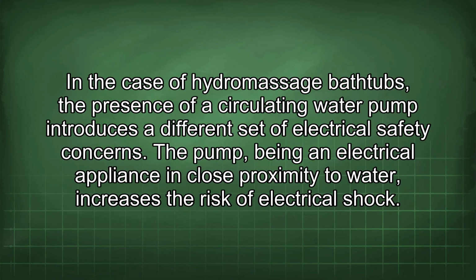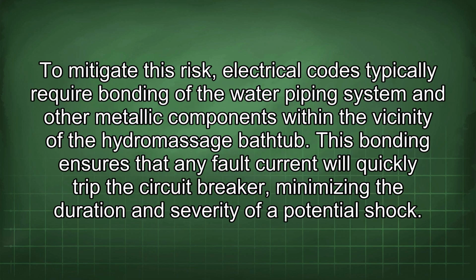In the case of hydromassage bathtubs, the presence of a circulating water pump introduces a different set of electrical safety concerns. The pump, being an electrical appliance in close proximity to water, increases the risk of electrical shock. To mitigate this risk, electrical codes typically require bonding of the water piping system and other metallic components within the vicinity of the hydromassage bathtub. This bonding ensures that any fault current will quickly trip the circuit breaker, minimizing the duration and severity of a potential shock.